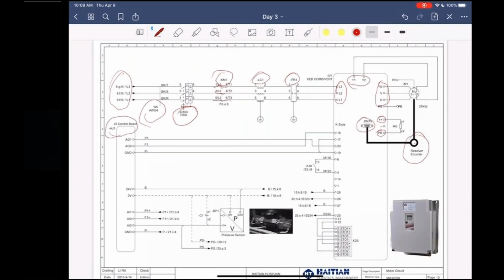J5 or AJ1 control board, that's the card that's getting the control from the pressure sensor that's located on the manifold. So whatever pressure is seen in the system or velocity or flow, it sends that information to this AJ1 card, and that information goes back to the KEB drive.